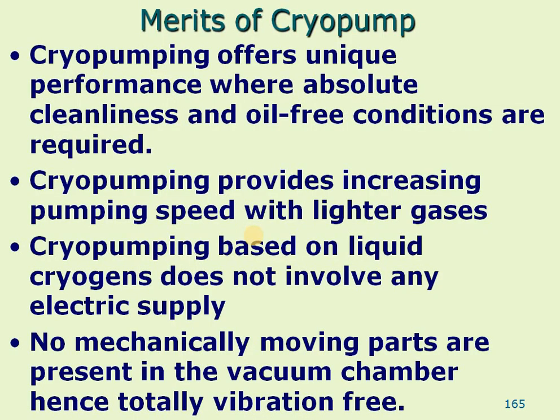This is the most advanced level of pump, used in modern high-end experimental applications. Cryogenic pumps offer unique performance. They provide absolute cleanliness and oil-free conditions. Their pumping speed is tremendously high, and lighter gases like hydrogen and helium — which are difficult to pump in rotary or diffusion pumps — can easily be pumped here.